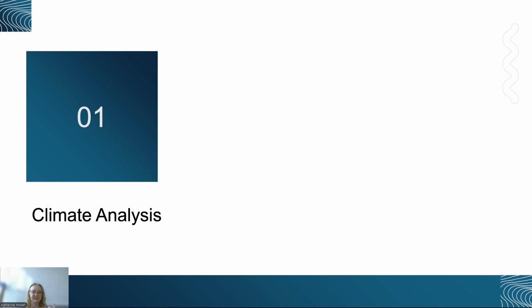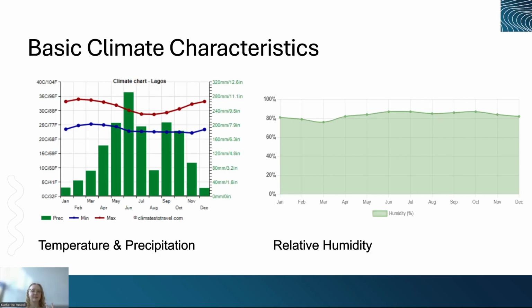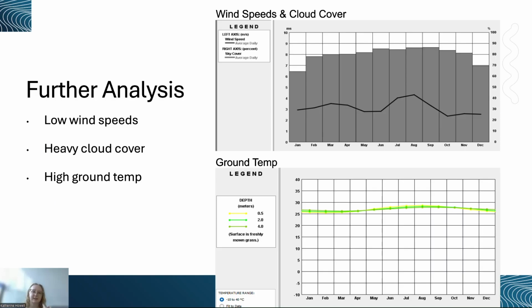For our climate analysis, as you can see, Lagos is very hot year-round and also very humid. The average monthly high is between 35 and 27 degrees Celsius, and the low never reaches 20 degrees Celsius. The high rainfall centered around June, along with the coastal location, means that the relative humidity hovers around 80% all year long. Further analysis, there are low wind speeds and heavy cloud cover year-round, and because of the consistent climate, the ground temperature hovers above 25 degrees Celsius, even 4 meters beneath the surface.